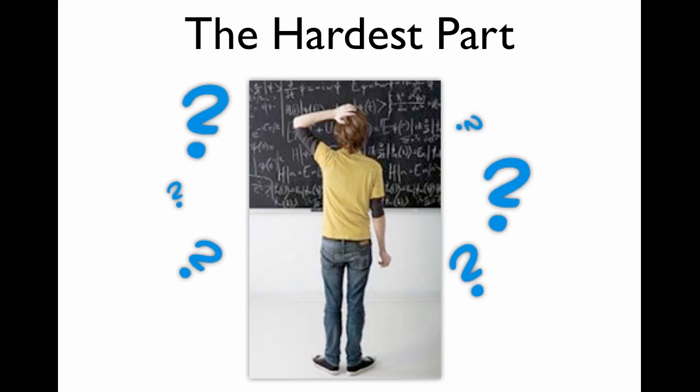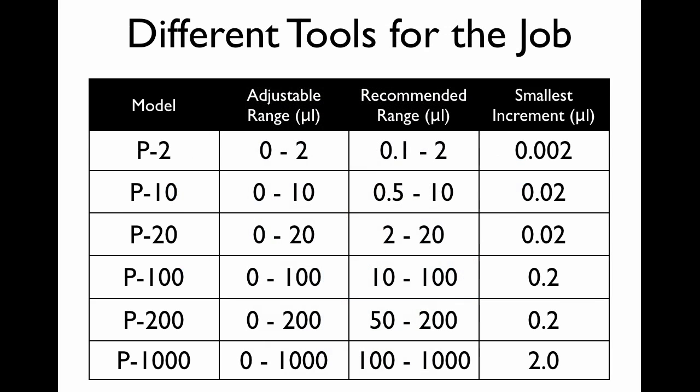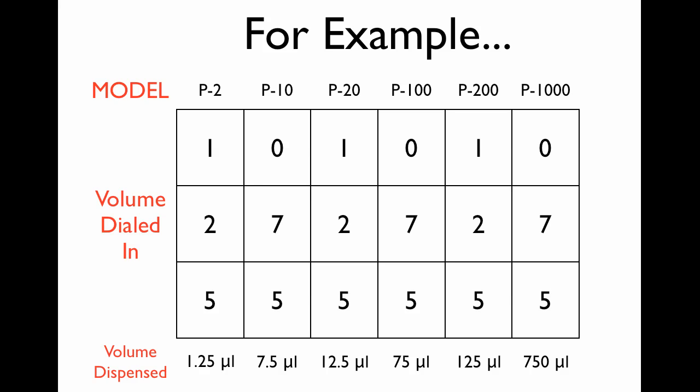The hardest part of using a micropipetter is really knowing which pipetter to use and what the volume is that you're going to dial in. So there are a variety of models that will help you to dispense the volumes that you want. But you've got to pay attention to what you're using and how you dial them in. So this gives you the adjustable range of each of the models, the recommended range. In other words, this is the column that shows with high accuracy what you can actually pipette. And then the smallest increment here that you can actually adjust to. Now, I know this is confusing, but you might want to spend some time looking at this and pressing pause so that you understand what this actually means.